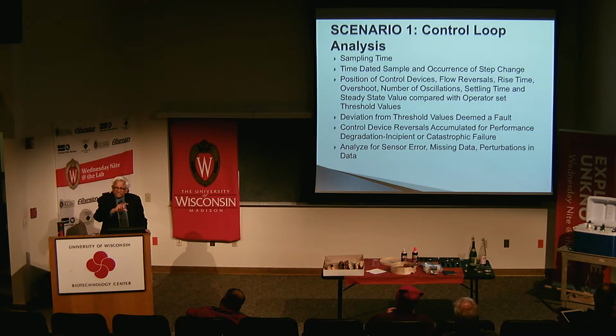The operator can set thresholds. He may not want more than 2 oscillations. Now, whenever you have oscillations, imagine a cooling coil. That means the valve opens and closes, opens and closes. So there is a possibility after thousands of such closes, you may have an incipient failure. Depending on the manufacturer's data for this repeated on and off cycling, there's a chance that the valve may fail. So you can issue a command to the operator. Maybe it's time to change the valve. You can change it during an unoccupied period or a weekend or so. So the operator sets the threshold value for faults.